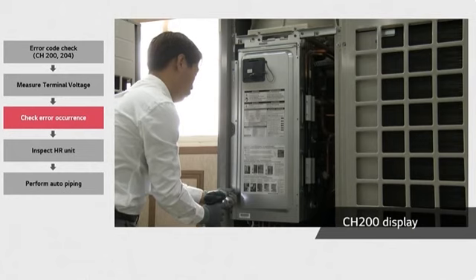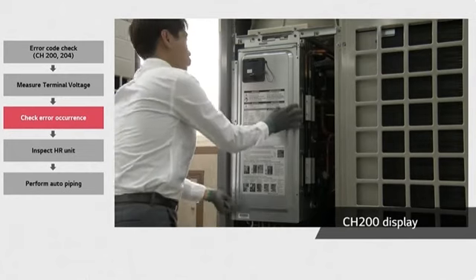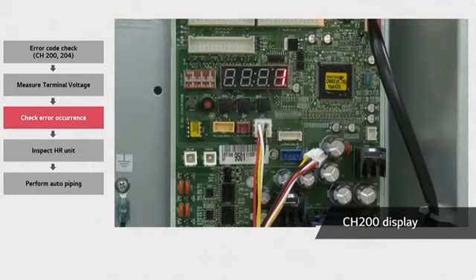Then disassemble the control box cover of the outdoor unit. You can check the error number on the ODU's PCB. If it is error CH200, the number 200 will be displayed on the PCB screen.